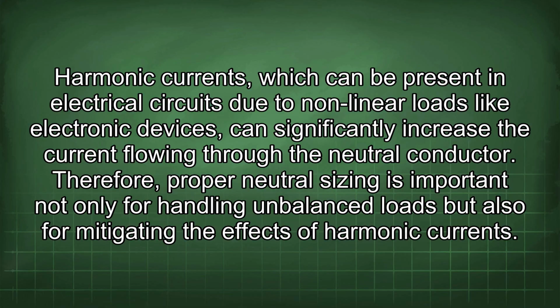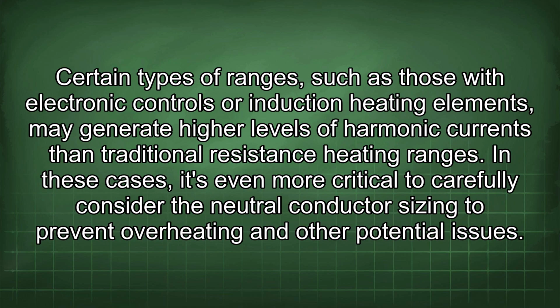Harmonic currents, which can be present in electrical circuits due to nonlinear loads like electronic devices, can significantly increase the current flowing through the neutral conductor. Therefore, proper neutral sizing is important not only for handling unbalanced loads but also for mitigating the effects of harmonic currents. Certain types of ranges, such as those with electronic controls or induction heating elements, may generate higher levels of harmonic currents than traditional resistance heating ranges.